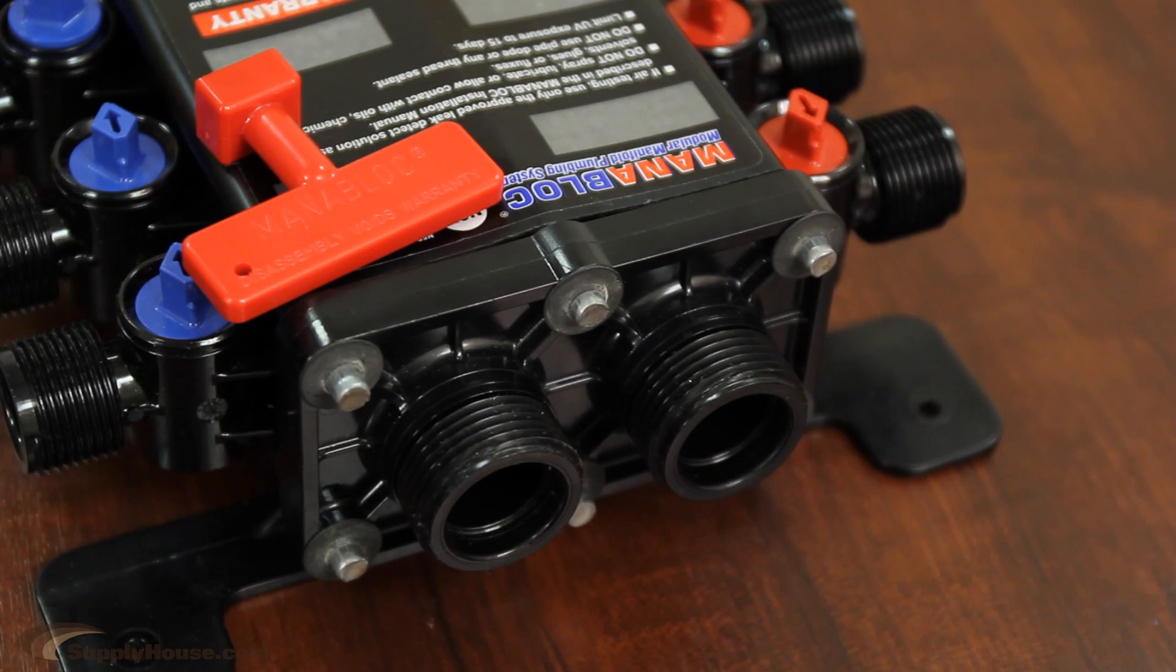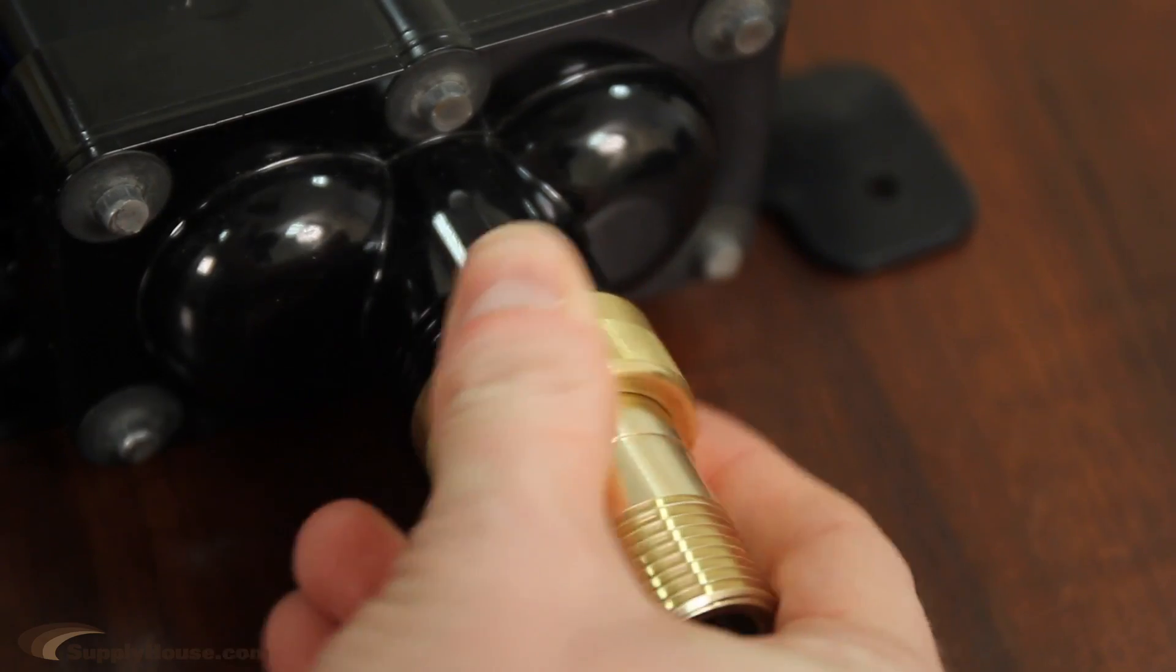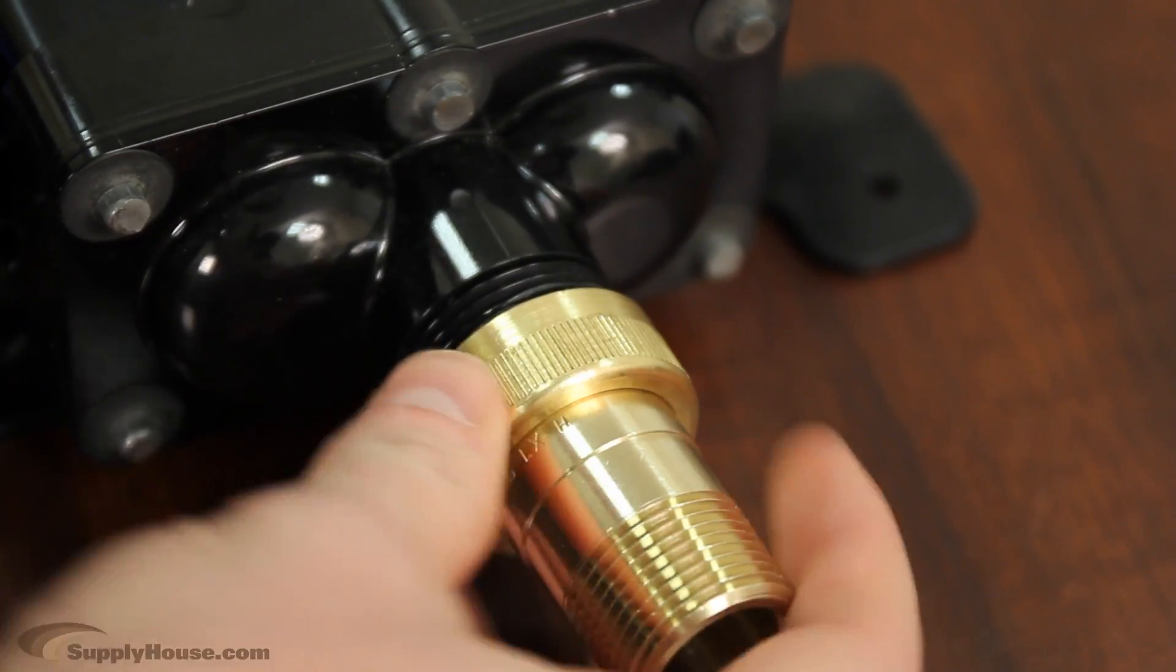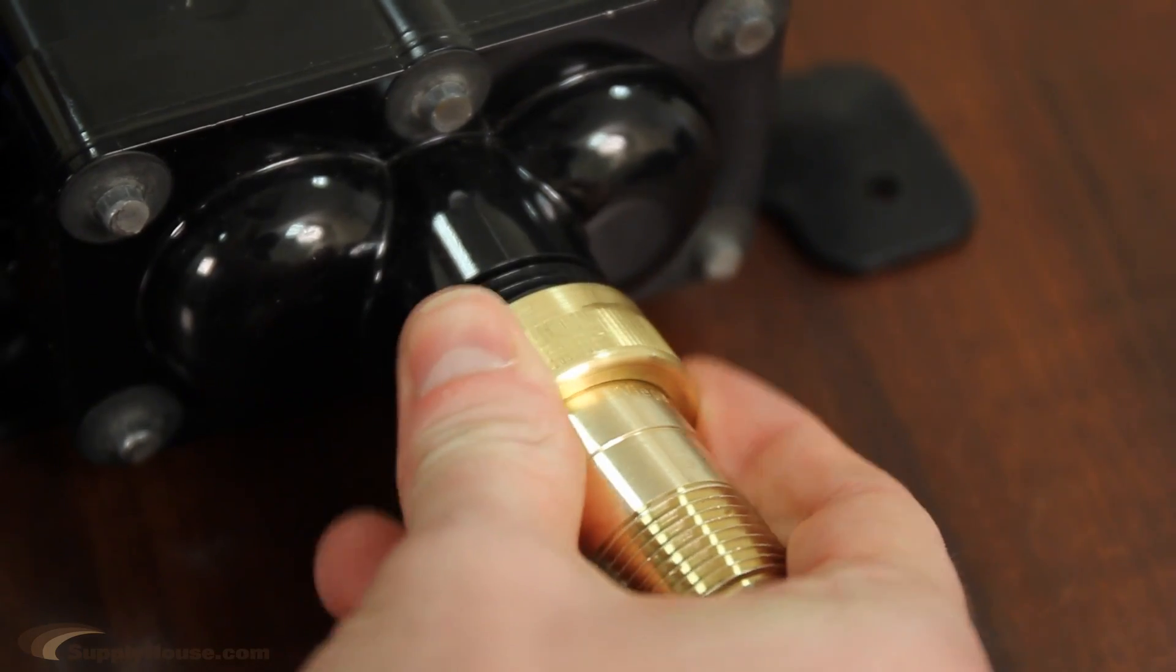The problem typically occurs when connecting the supply adapter to whichever supply port they have on the bottom of the ManaBloc. They're taking the supply adapter and because it's on the bottom, they're working against gravity, pushing against it and it's not screwing on straight.